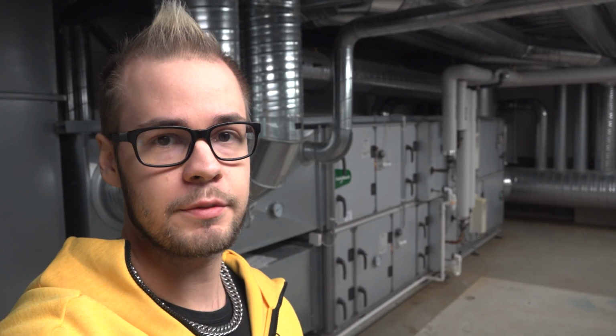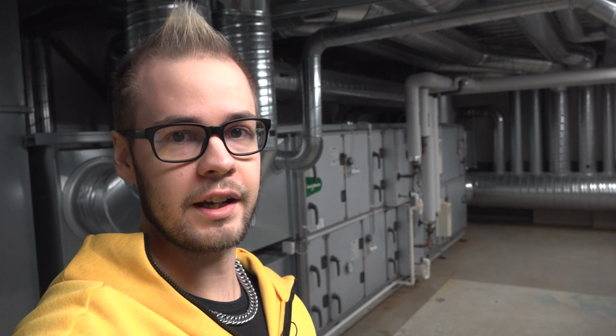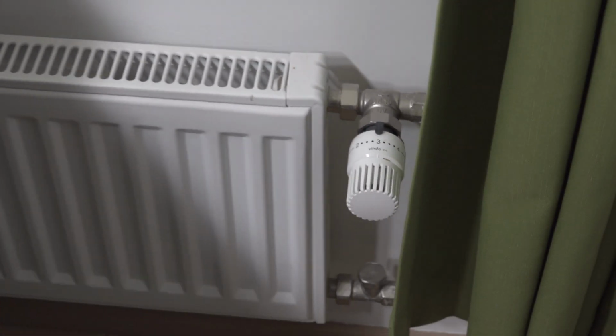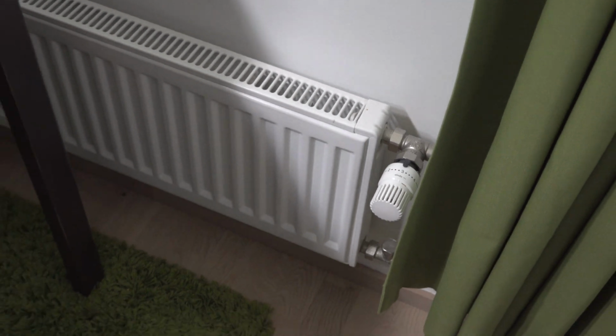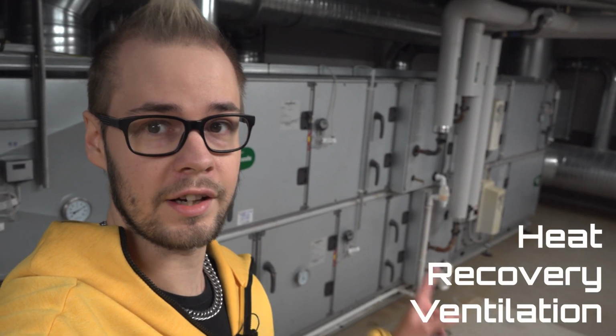Today we're taking a look at a piece of engineering that I find very interesting. It's a system called mechanical heat recovery system in the ventilation unit. It makes our apartment building's central heating crazy efficient. It lowers our heating bill quite a lot during the winter. If the outside temperature is more than -5 degrees, we don't have to import any energy for the heating of the input air. We still need some energy to heat up the radiators and whatnot, but the heating of the air is done pretty much completely by the HRV system you see here.